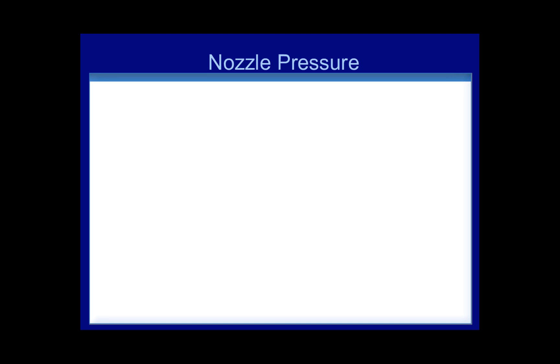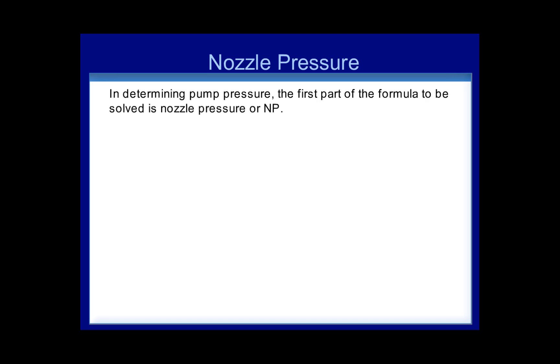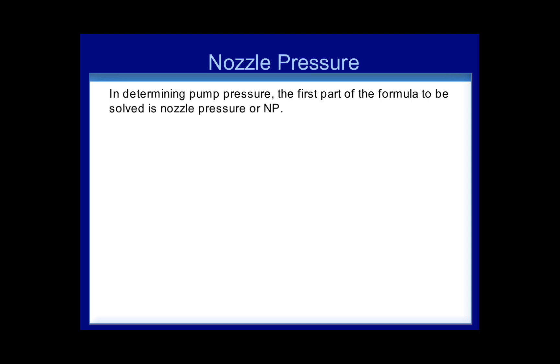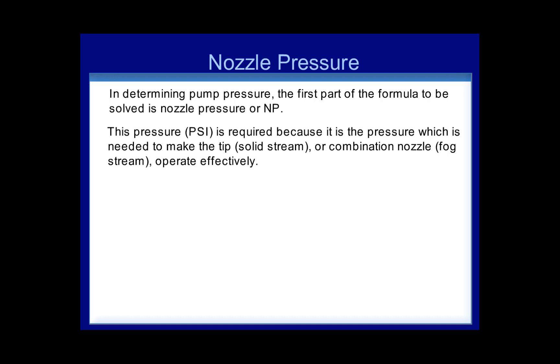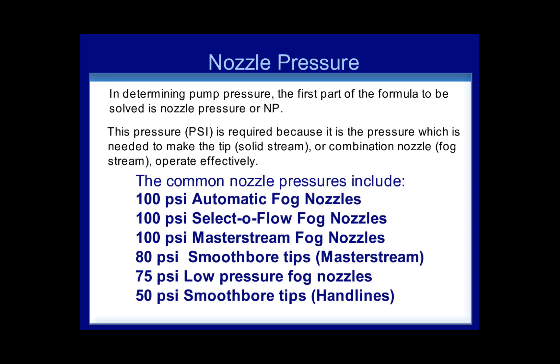Nozzle pressure. In determining pump pressure, the first part of the formula to be solved is nozzle pressure, or NP. This pressure, or PSI, is required because it is the pressure needed to make the tip of a solid stream or combination nozzle fog stream operate effectively. Common nozzle pressures include 100 PSI for automatic fog nozzles, 100 PSI for a selectoflow fog nozzle, 100 PSI for master stream fog nozzles, 80 PSI for smoothbore tips for a master stream, 75 PSI for low-pressure fog nozzles, and 50 PSI for smoothbore tips on handlines.